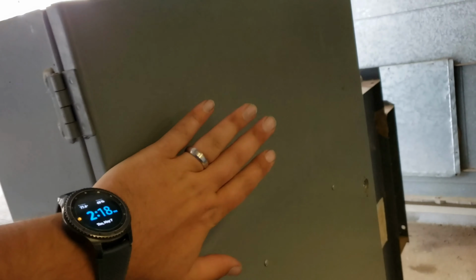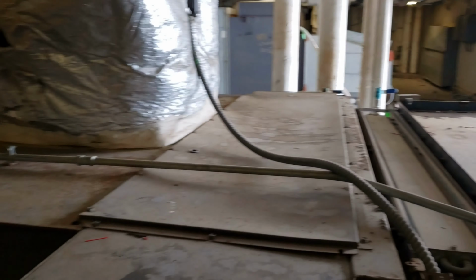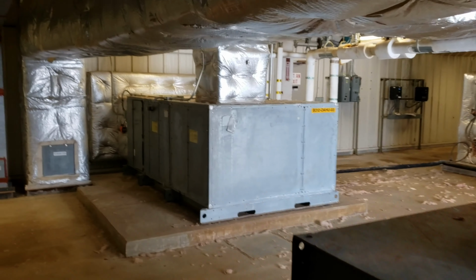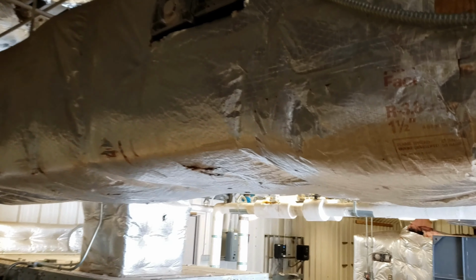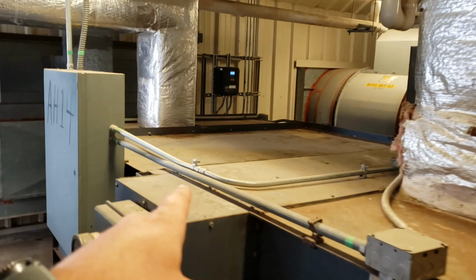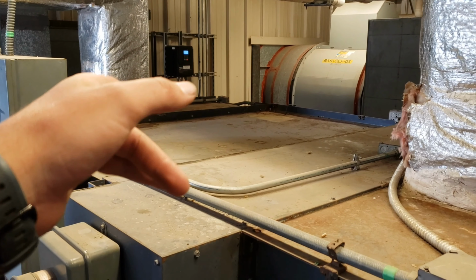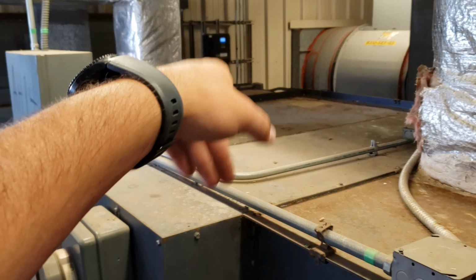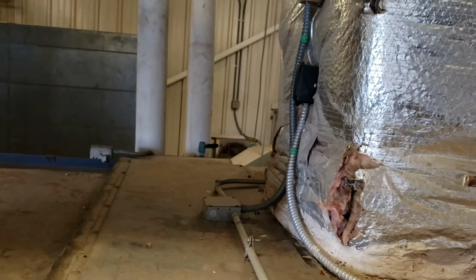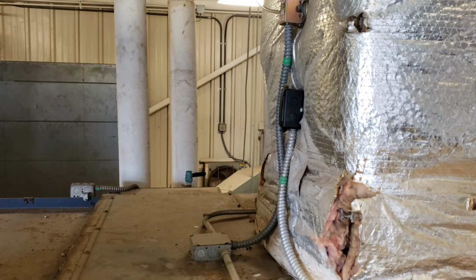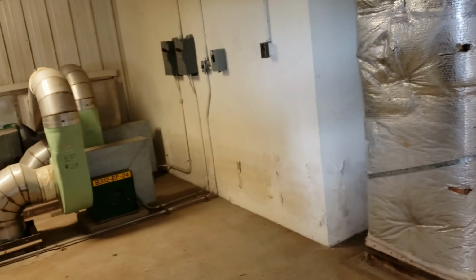This air handler here ended up having an issue with just some loose connections up through here, so we got that addressed. It's now firing correctly. This one here, there was a wiring issue where it was not killing the drive over there in the corner, and then the high static had tripped, and again it was bypassed, and so got that resolved, but that was why it wasn't shutting down.